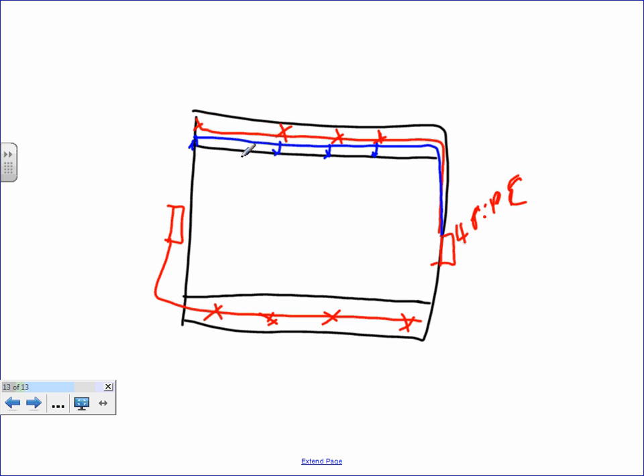If you're not doing VESDA, you're looking at smoke detectors. Basically, you're running the wiring the same, the pipe is the same, and each of these sampling points is a smoke detector instead. And you're going to have 2 circuits: above the drop ceiling, in the ceiling, and then below the raised floor.